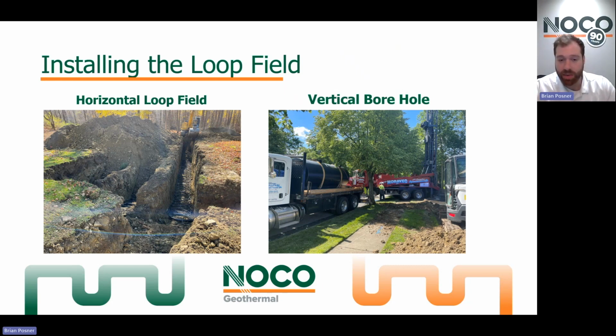You get your heat exchange piping in the ground. This is usually done through a horizontal loop field or a vertical borehole. A horizontal loop field is done where you have a lot of excess land and you can afford, say, a 40-foot by 80-foot footprint being dug up, piping being installed, and then covered back up. That's assuming you have no septic system under that ground. You have no utility lines. You need a free and clear area of land that's at least 40 feet by 80 feet to do a horizontal loop field. In that loop field, you get 80-foot long trenches that are 4 feet wide.